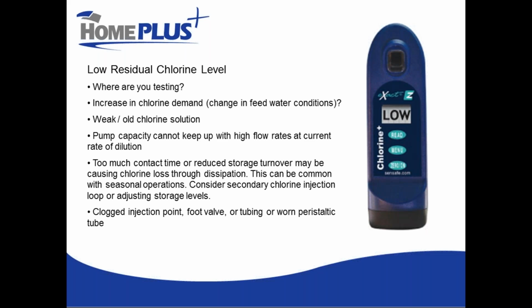Or you can potentially just lower the reservoir level in the winter. The engineer or designer of your system can give you new calculations to run at a lower level and get basically approval from the drinking water officer and public health engineer for those calculations, and then you just run your reservoir float or reservoir level control at a lower level during those periods. But too much contact time is actually a problem as well because the chlorine will dissipate.